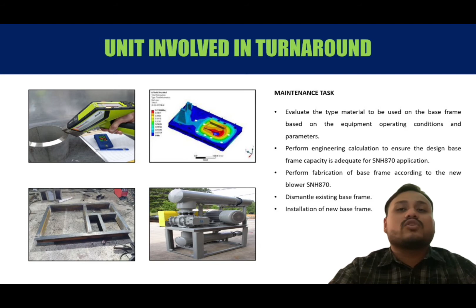SA, or site acceptance, should be agreed by both contractor and owner after the installation of the new base frame. And we shall perform a bump test or operational deflection shapes (ODS) during the commissioning, and after that modal analysis, to visualize the vibration pattern of the base frame as influenced by operating forces from the blower and motor. The natural frequency of the base frame shall not be excited by any forcing frequency from the equipment, and the contractor shall perform this scope for the new base frame.